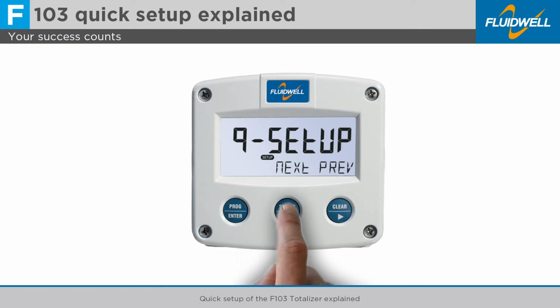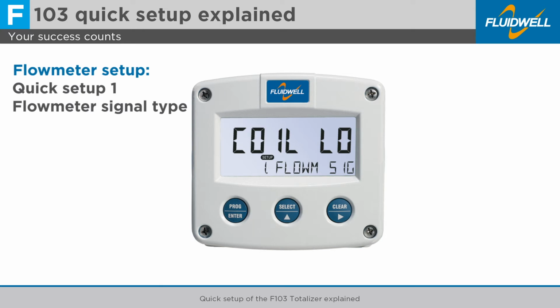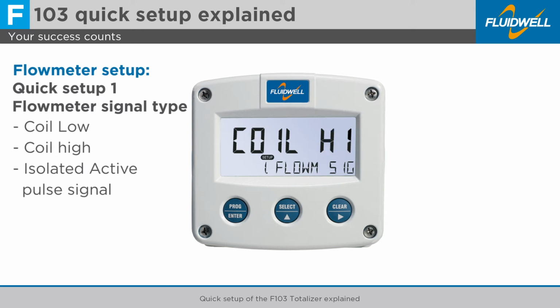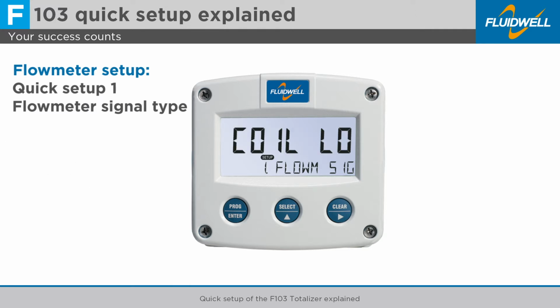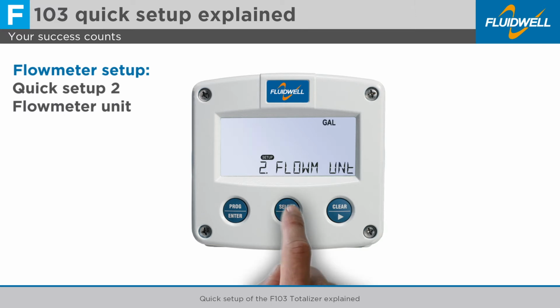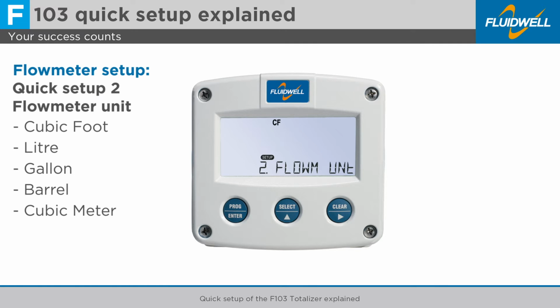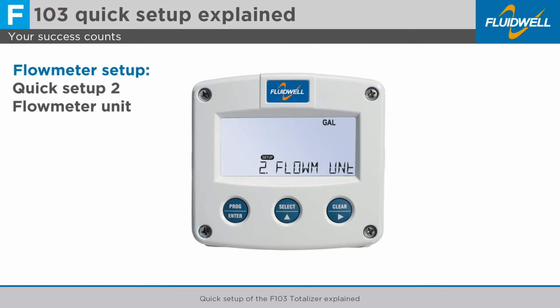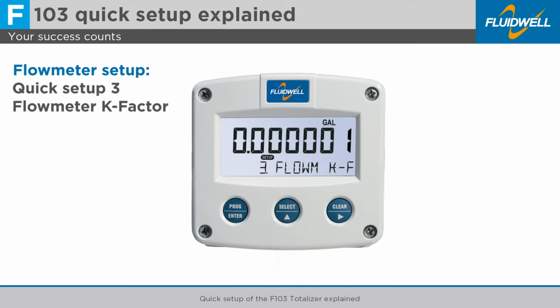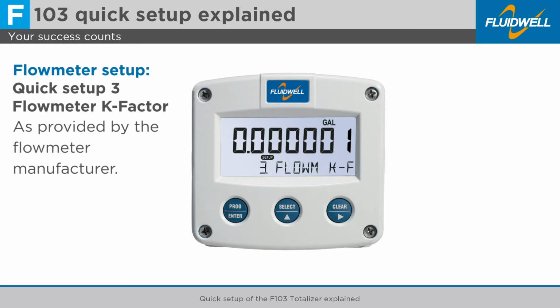Flowmeter setup. Quick Setup 1. Here you can set the flowmeter signal type, coil low, coil high, or isolated active pulse signal. Quick Setup 2. Here you can set the calibrated measuring unit for the flowmeter, cubic foot, liter, gallon, barrel, or cubic meter. Quick Setup 3. Here you can enter the K-factor for your flowmeter as provided by the flowmeter manufacturer.